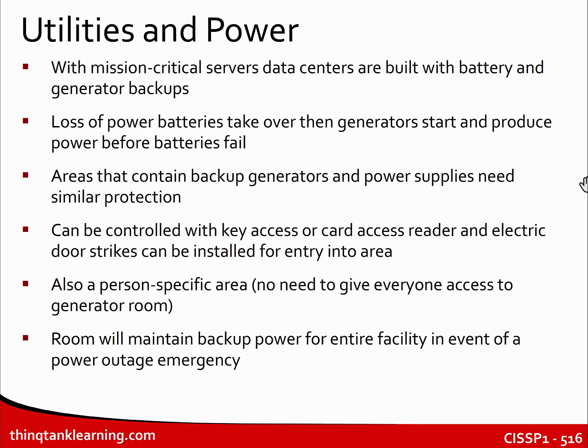We would often go out when I was working at NASA — we had generators and backup power systems everywhere, and we'd test those power systems every month, running the generators every month. There's liquids inside those generators; they're basically diesel truck engines. If something sits stagnant for a long time, it gets gummed up and doesn't work. So we run the generators every once in a while, and even test the switchover systems and the intelligence behind them.